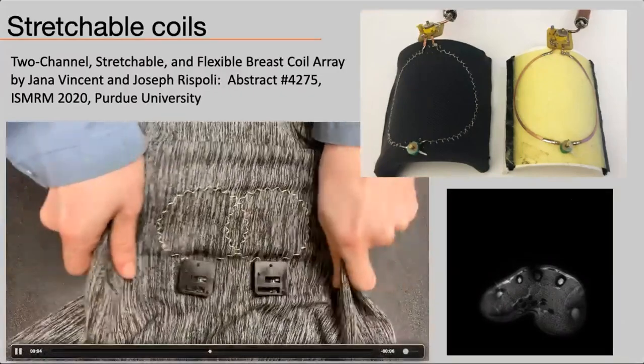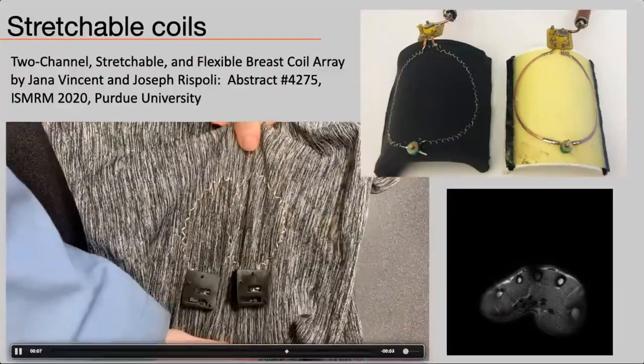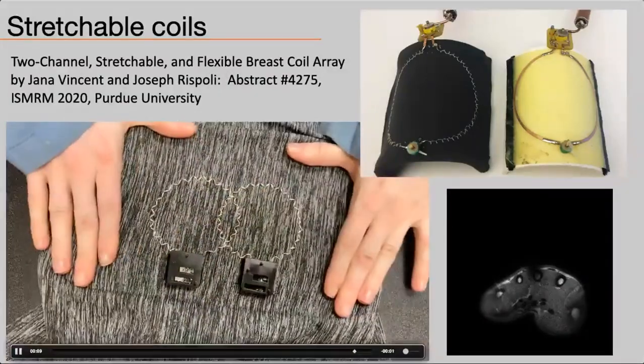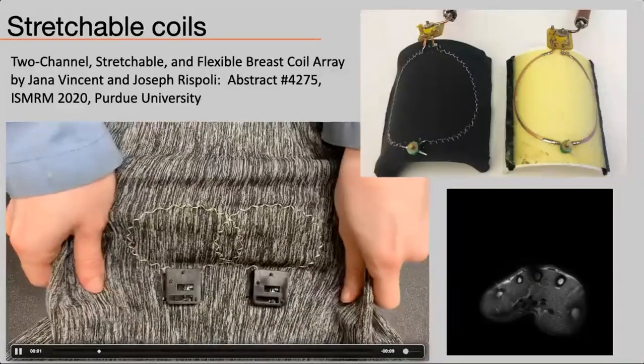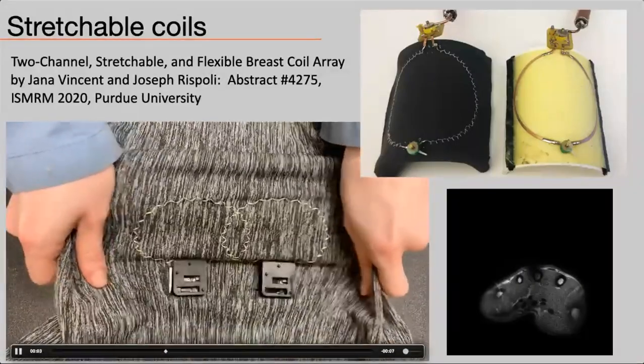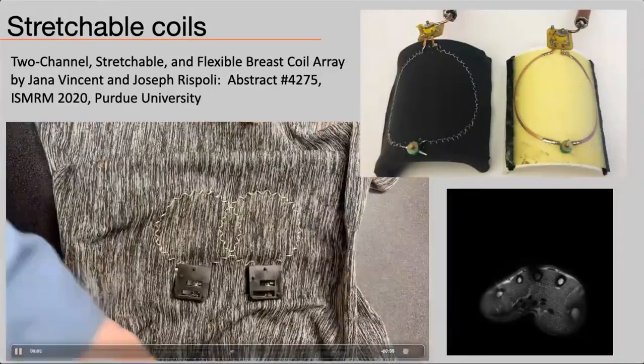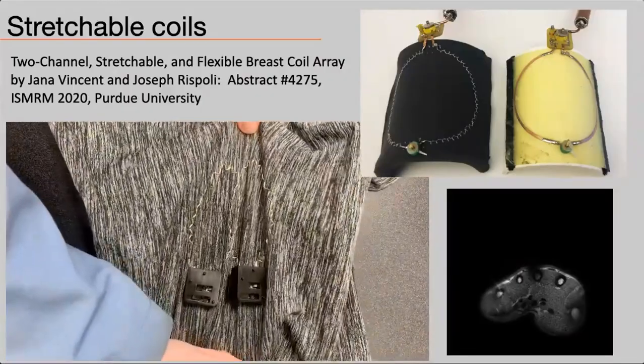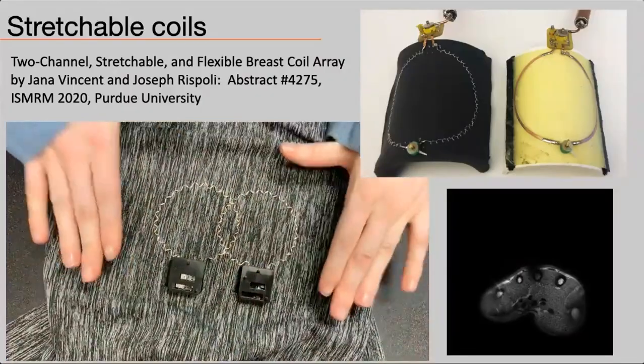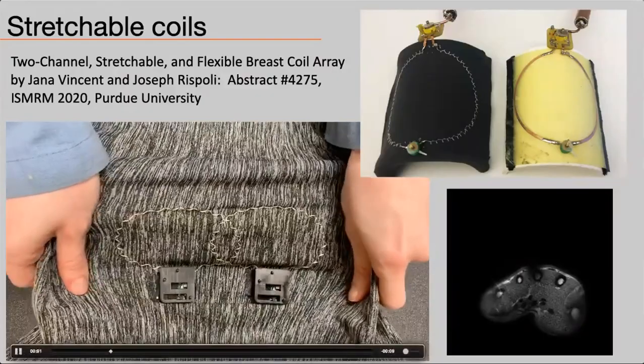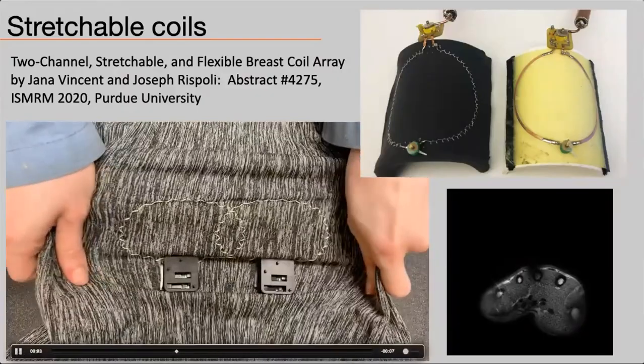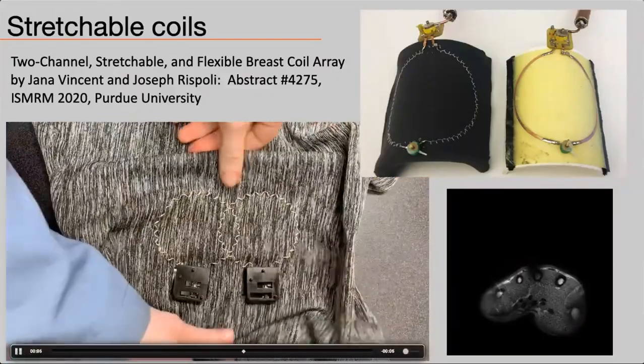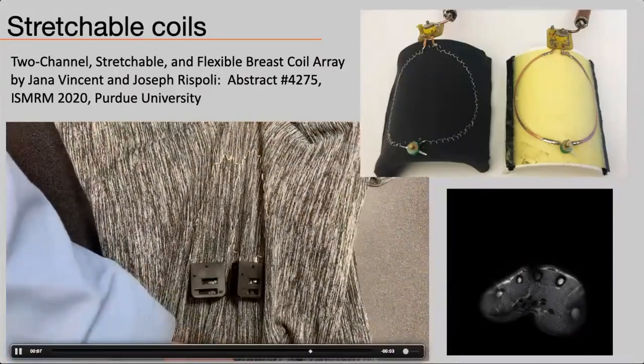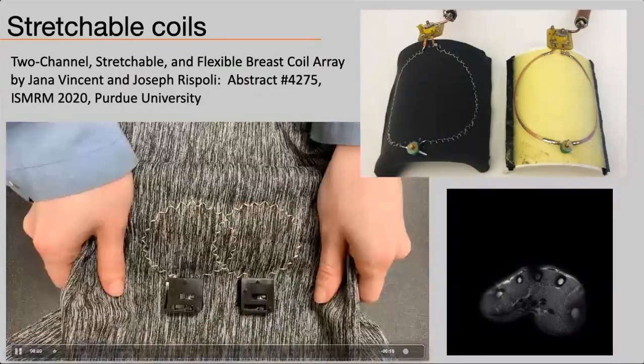Any change in geometry can cause a change in resonance or coupling. So the fact that you change the geometry of the coil means you're going to change the inductance and the resonance frequency. This is somewhat mitigated by the matching circuitry and preamplifier decoupling. Basically, your electronics afterwards tries to mitigate some of those issues, albeit with some limitations.